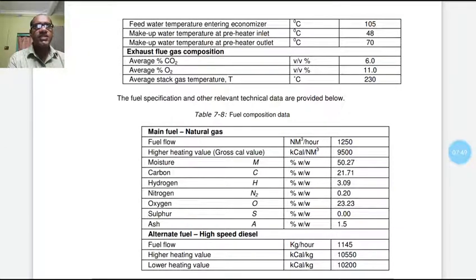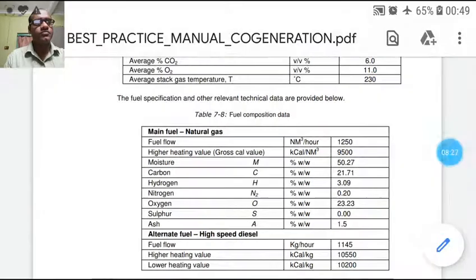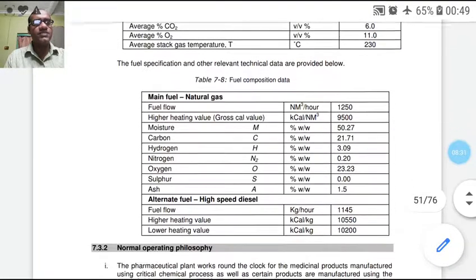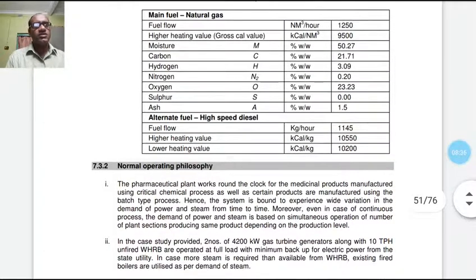The fuel specification and other relevant technical data are also provided. Main fuel is natural gas, with fuel flow 1250 Nm³ per hour. HCV value 9500, moisture content 50.27, carbon content, hydrogen, nitrogen, oxygen and sulfur contents are given, and sulfur in this case is 0. Ash content is very low, 1.5. Now the alternative fuel used is high speed diesel: fuel flow 1145 kg per hour, higher heating value 10,550 kilocalorie per kg, and lower heating value 10,200 kilocalorie per kg.